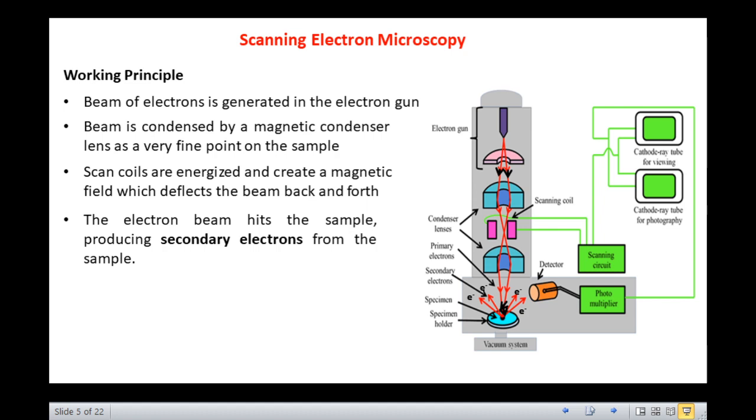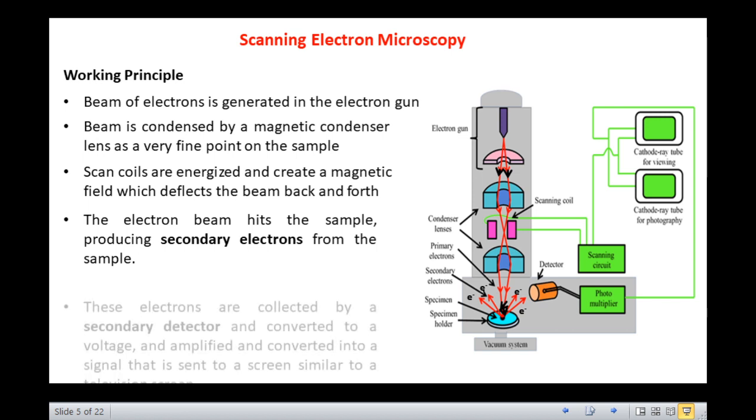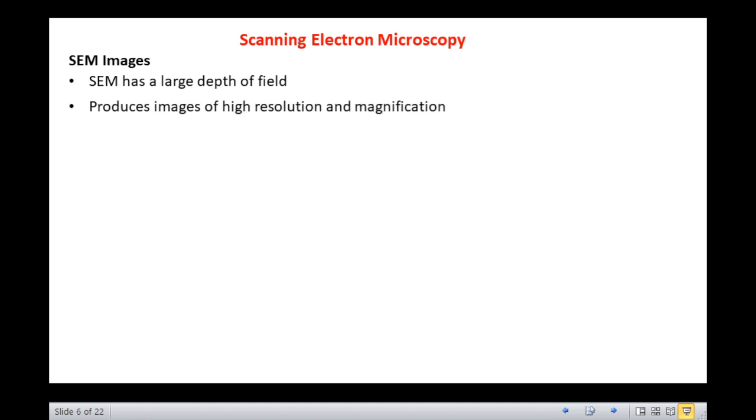The intensity of this secondary radiation is dependent on the angle of inclination of the object's surface. These electrons are collected by a secondary detector or backscatter detector, converted to a voltage, amplified and converted into a signal that is sent to a screen similar to a television screen. This produces the final image. The SEM has a large depth of field which allows a large amount of the sample to be in focus at one time.